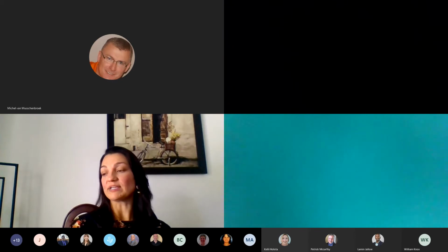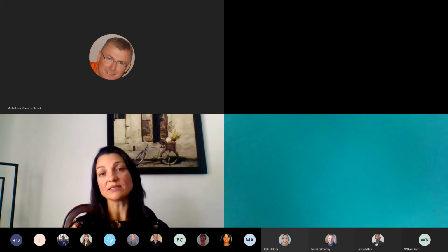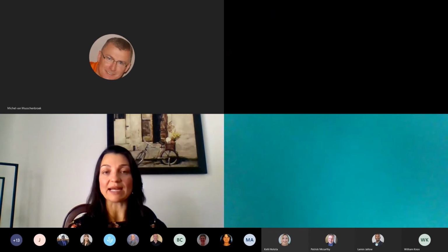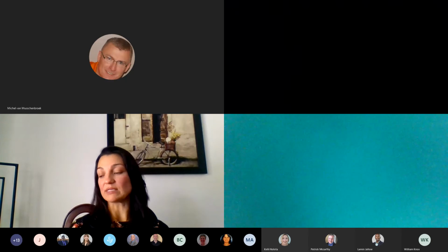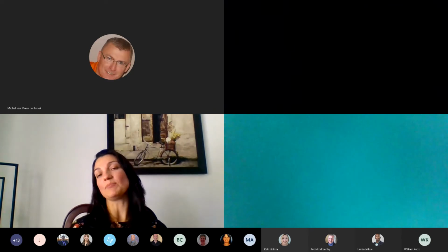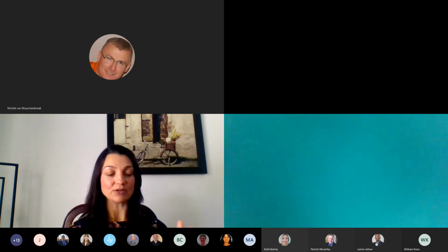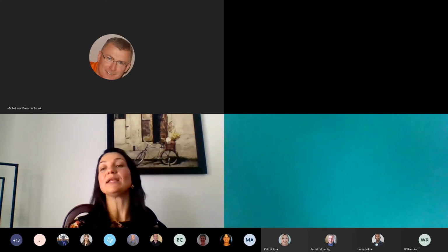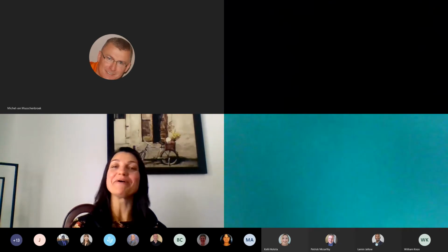So we test the instrument and say, before this instrument went out of commission, it was found within specification and in working order, and then we're retiring it. We issue a closing report, so you'd have the documentation from the installation of that equipment all the way to when it was retired. It's almost like a death certificate, if you will.